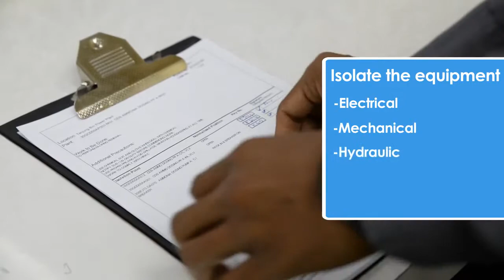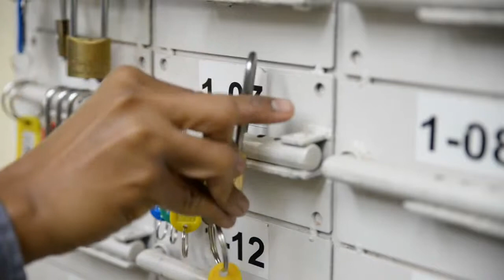Isolate the equipment according to electrical, mechanical, hydraulic, pneumatic, or steam type. Apply the isolation tag to the isolation point and comply with lockout-tagout procedure, or LOTO. Check all the isolated equipment through the isolation list before starting work.